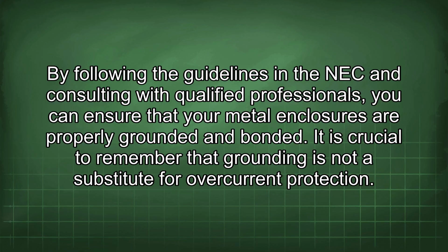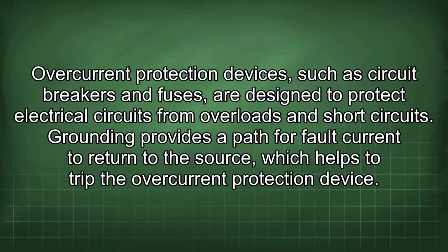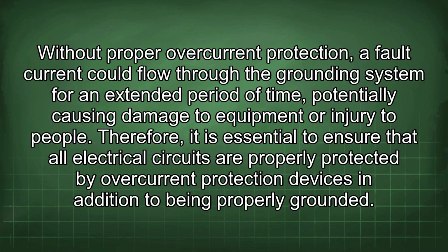properly grounded and bonded. It is crucial to remember that grounding is not a substitute for overcurrent protection. Overcurrent protection devices, such as circuit breakers and fuses, are designed to protect electrical circuits from overloads and short circuits. Grounding provides a path for fault current to return to the source, which helps to trip the overcurrent protection device. Without proper overcurrent protection, a fault current could flow through the grounding system for an extended period of time, potentially causing damage to equipment or injury to people.